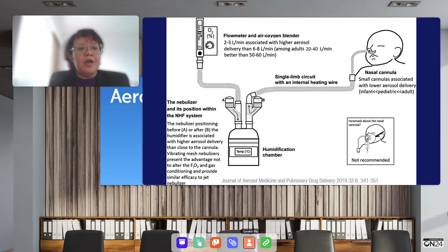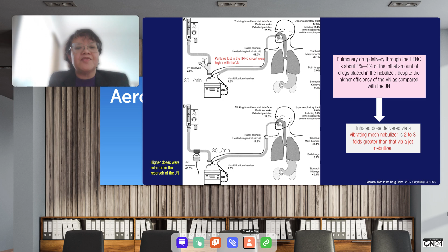And jet nebulizers can be placed in line before the heated humidifier. However, the inhaled dose delivered via mesh nebulizer is 2 to 3 folds greater than that via a jet nebulizer. And there are studies comparing the effect of salbutamol administered with high flow with mesh nebulizer versus jet nebulizer alone on lung function in patients with stable COPD. The bronchodilator therapy via the mesh nebulizer in line with the high flow was not inferior to jet nebulizers. And mesh nebulizer in line with the high flow improved the airway oscillatory mechanics, indicated by the lower respiratory resistance, area of reactance and resonance frequency, and reactance compared to jet nebulizer.